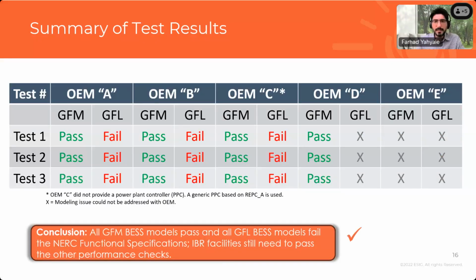Here's a summary of the test results at a high level. We tested 5 different OEMs, and for confidentiality, the names are removed and we use letters A, B, C, D, E. In general, all the GFM models provided by the OEMs passed the NERC functional specification, and all the GFL, or grid following, models failed the test. There were some issues with some models that we were able to resolve. Unfortunately, 2 of the OEMs had issues with some of their models that they were not able to resolve.